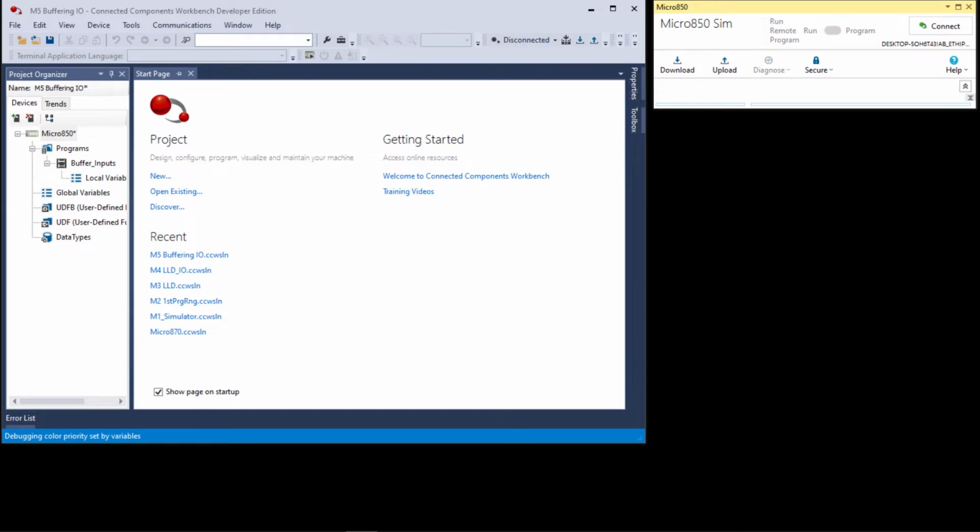Then it executes all the logic in your programs. Then it takes any output memory locations that have a DO instead of a DI. By now you've used at least one of those. It updates those at the end of the program scan. In other words, those bits are set during the program scan.